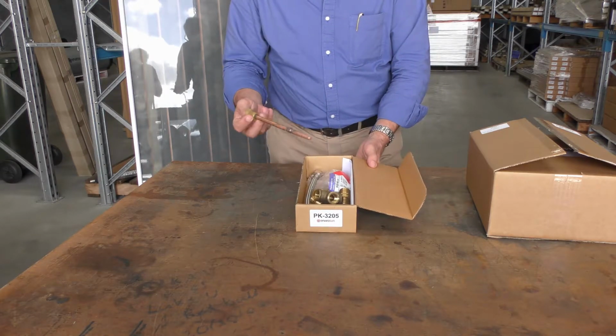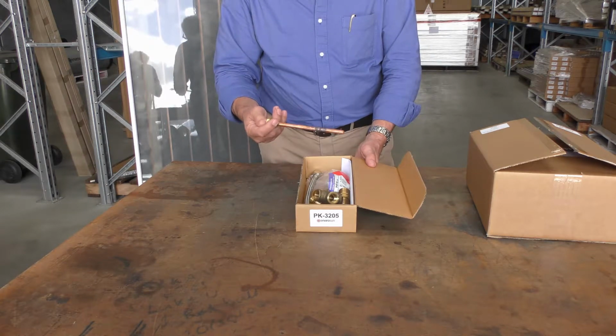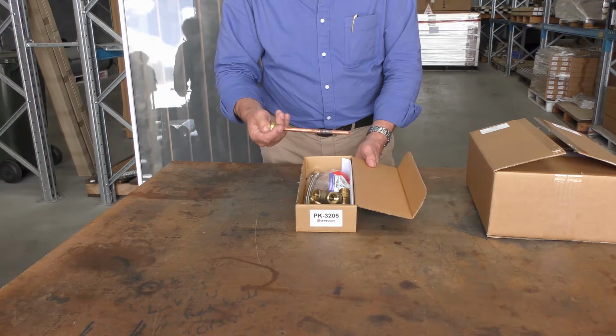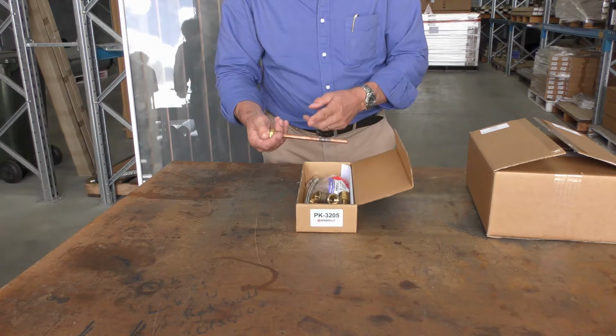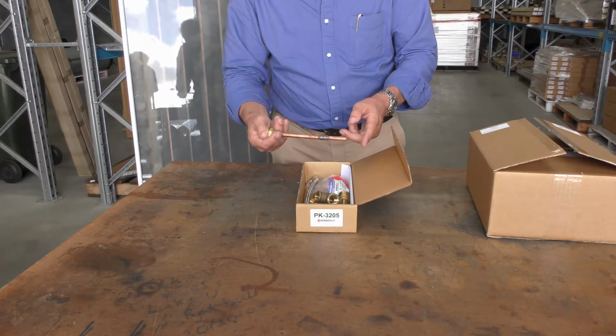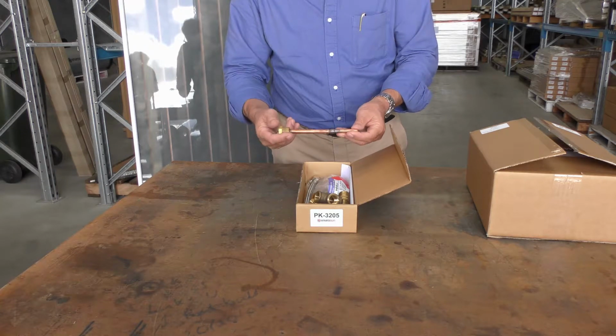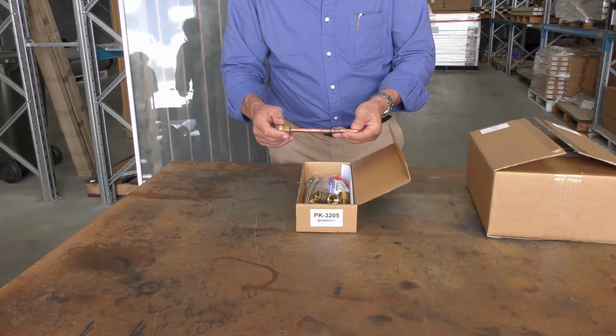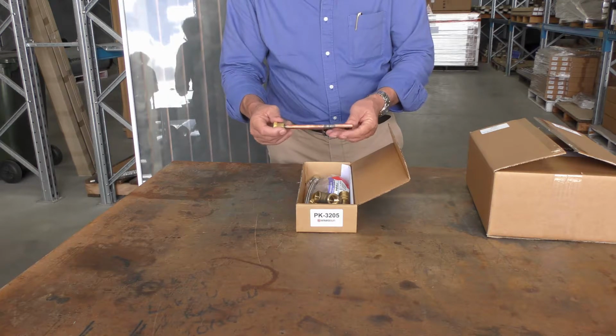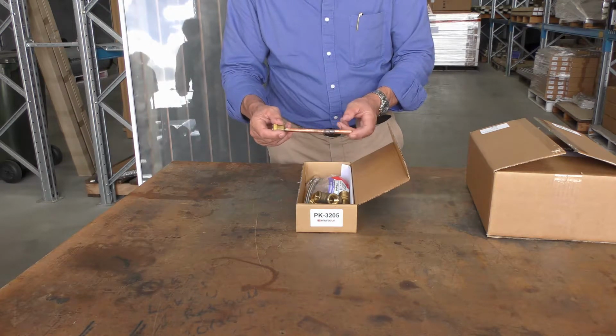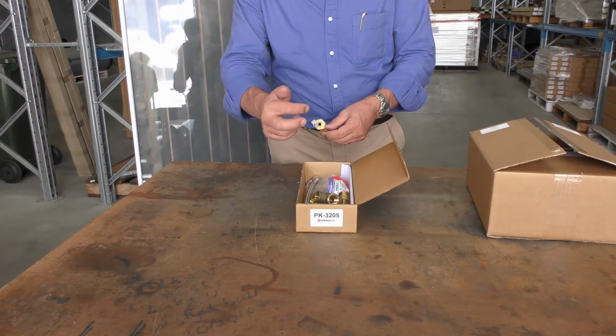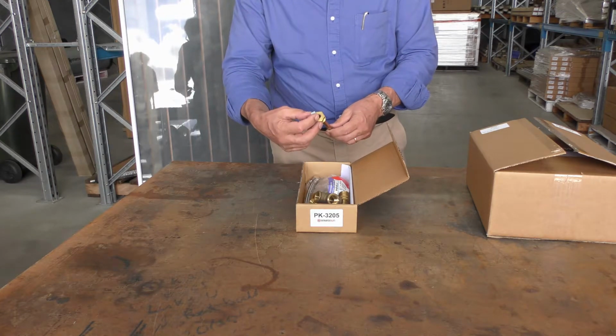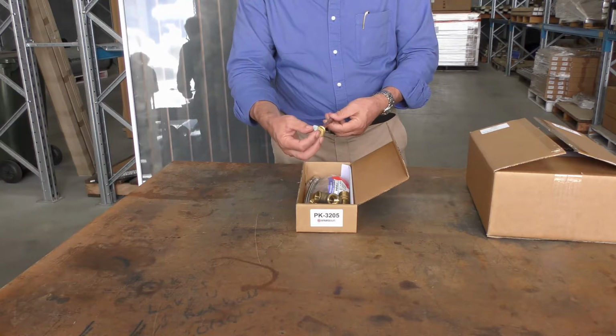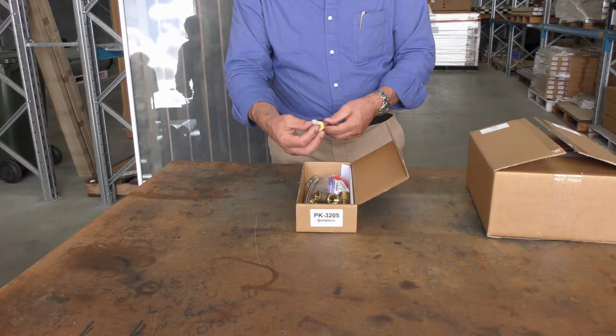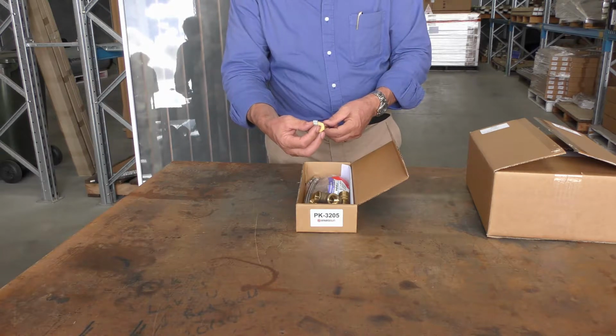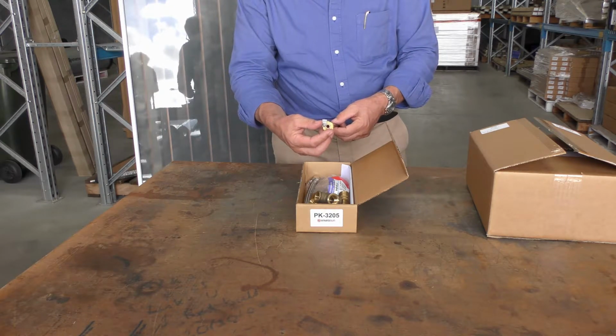First, we've got a temperature probe. I showed you the temperature probe for the hot side earlier; this is the cold temperature probe. It can't be as long as the other one - we used to make them longer once, but these are much shorter because the water dip tube inside the tank doesn't allow it to go any further than this distance. We put the cold sensor into this, slide it in, and then put this little P-clip around it to stabilize it so it can't be pulled out and lose the ability to sense the correct temperature.